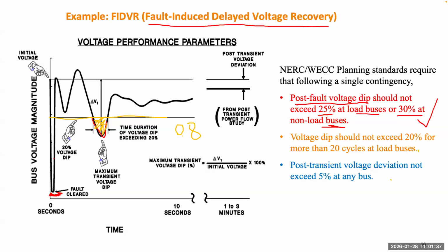If this is satisfied, the last sentence says that after some time, usually maybe tens of seconds or maybe 1 minute, the voltage needs to go back to this very narrow envelope. This envelope is 5% from the nominal value. So they need to go back to 0.95 and stay above 0.95. If this is satisfied, the entire transition is safe.